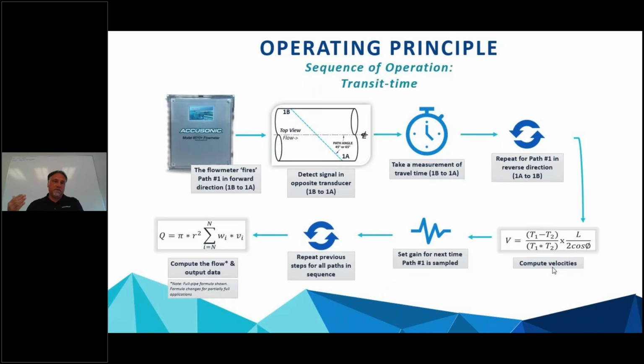So instead of going from the upstream to downstream transducer, now we are transmitting from the downstream to upstream transducer. We repeat that over and over again until all the paths are fired, and then all the travel times are recorded. And then we compute the velocities here over on the bottom right-hand side, where we have basically 3 variables to calculate velocity. We have the path length, that's the transducer face to transducer face measurement.